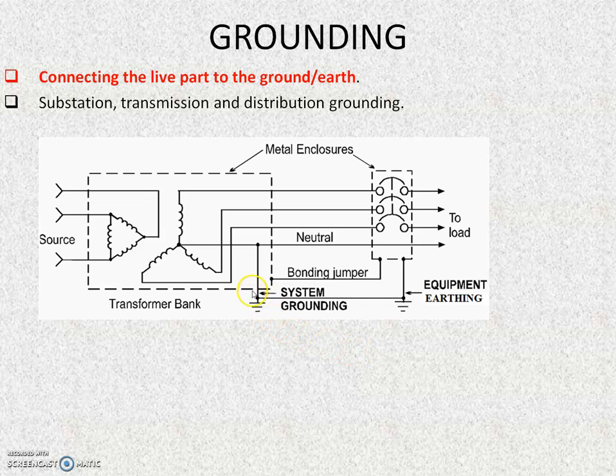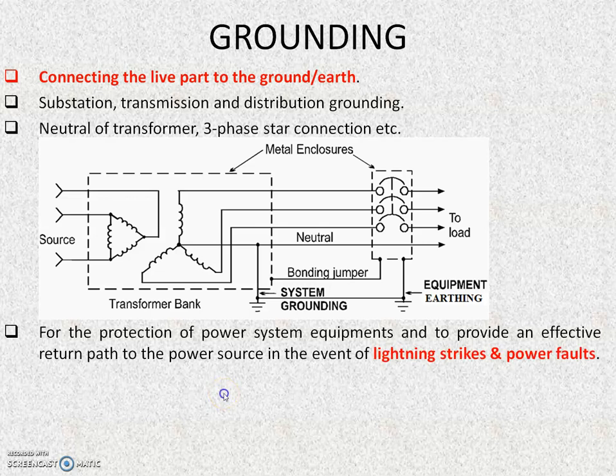So in this case, we can see system grounding and equipment earthing. In some cases, people used to call this equipment earthing and this system earthing. But normally in India, we call it equipment earthing and system grounding. So at the equipment level it is called earthing, and at the system level, it is called grounding. The neutral of a transformer, three-phase star connection, etc. are connected to the ground and it is called grounding or system grounding.